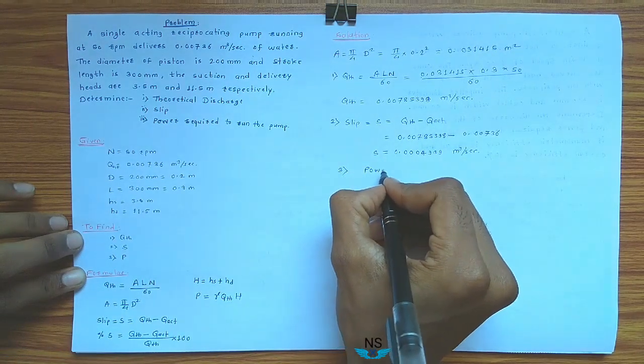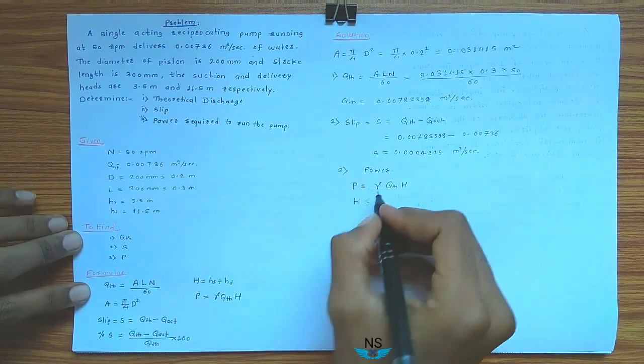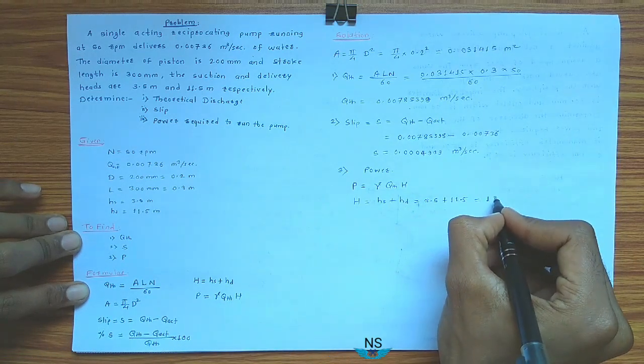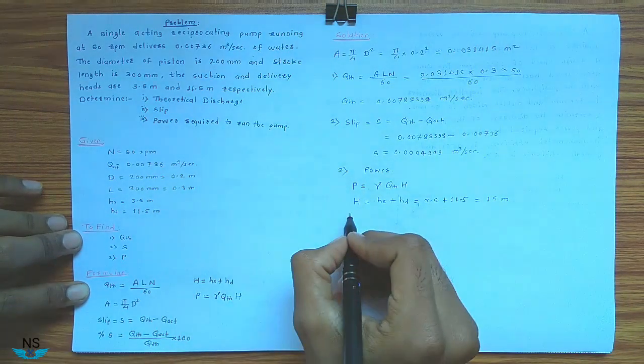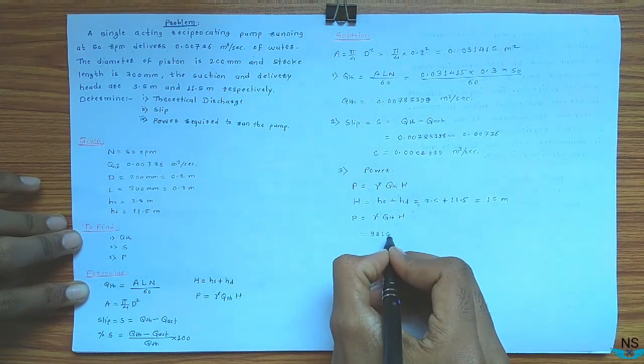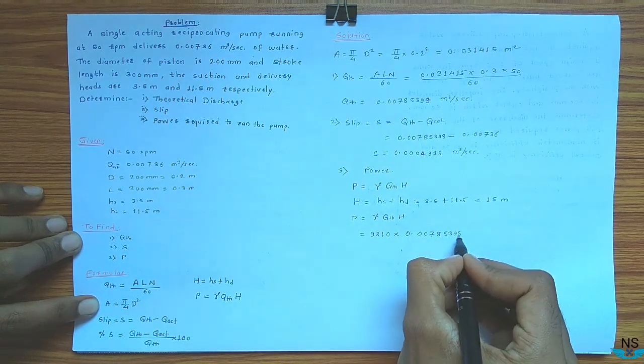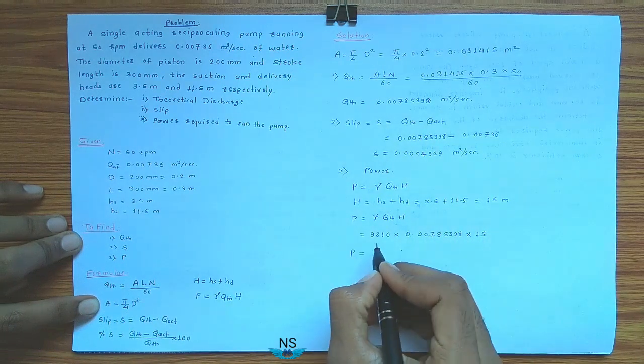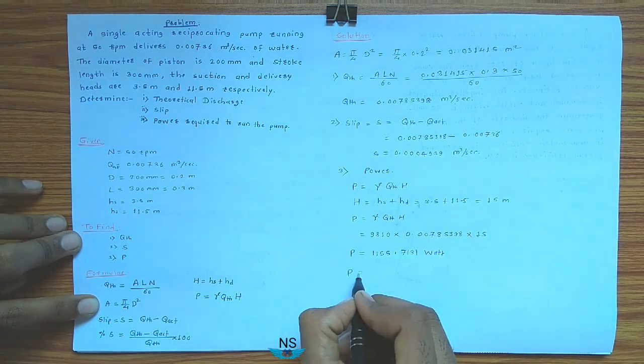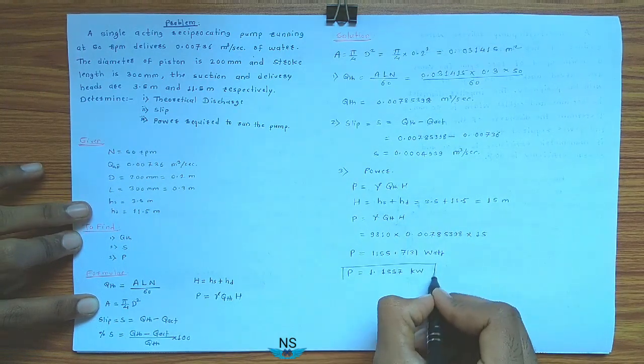Third, power required to run the pump: P is equal to γ into Q_theoretical into H. First find H: H is equal to HS plus HD, so 3.5 plus 11.5, which is equal to 15 meter. Now P is equal to 9810 into 0.00785398 into 15, so power P is equal to 1155.7 watt, or dividing by 1000, P is equal to 1.1557 kilowatt — this is the required power for the pump.